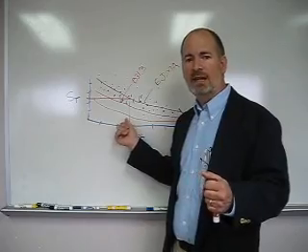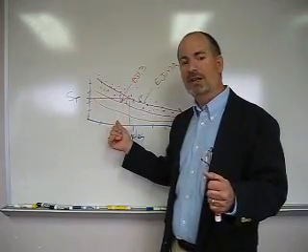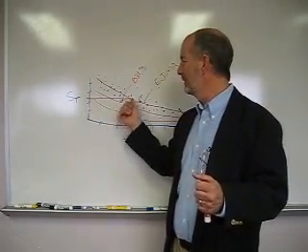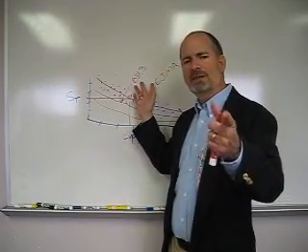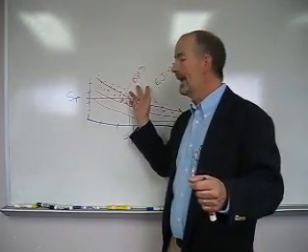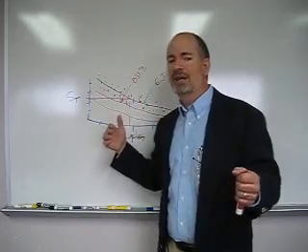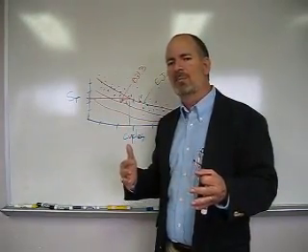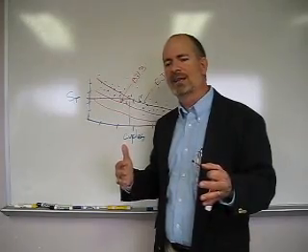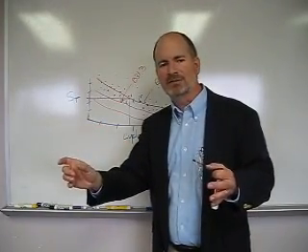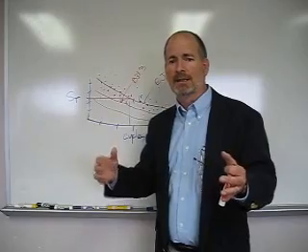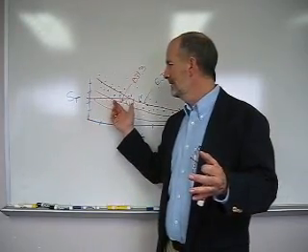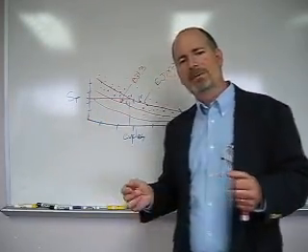So now you know, this is how fatigue curves are set up. This is the difference between B31.3 and EJMA. Before somebody out there interrupted me, B31.3 a lot of times, you'll see B31.3 imposed, but people have the presence of mind to say, but I want 7,000 cycles per EJMA. And they understand that, and they understand the factors of safety that we're throwing on here.